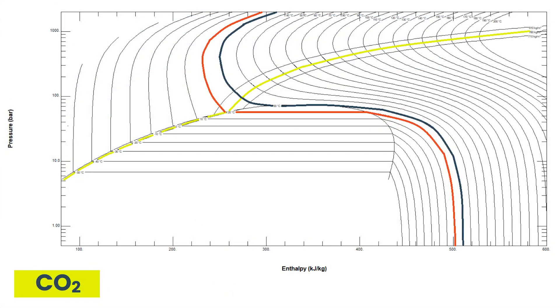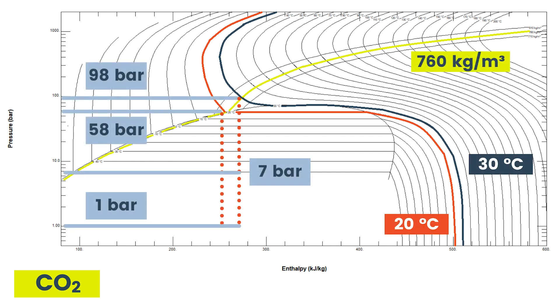So can we use carbon dioxide in our fridges and our air conditioners? Theoretically yes, practically and economically not really. There are likely industrial applications where carbon dioxide is a good choice as a refrigerant, but I don't really know much about them. But if you were to try and do it in your home, it isn't just like you could bleed off the current gas and replace it with carbon dioxide. You'd need a compressor that could deliver much higher pressure, components that could withstand these higher pressures, you wouldn't likely cool it to below its critical point at 31 degrees, and you'd also risk getting dry ice if you don't charge your system so that it was above 5.2 bar.